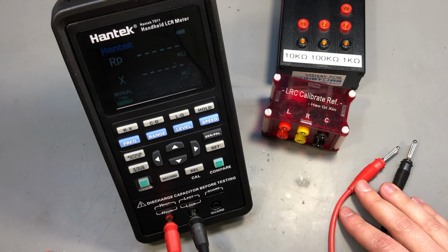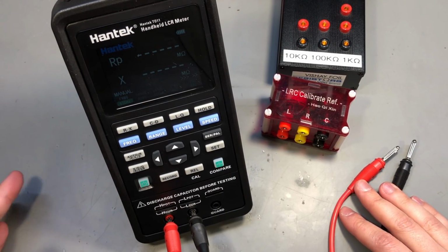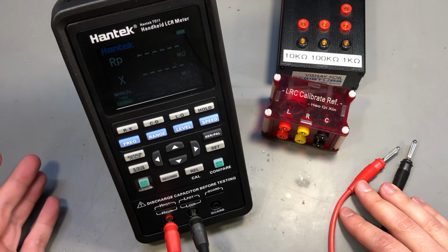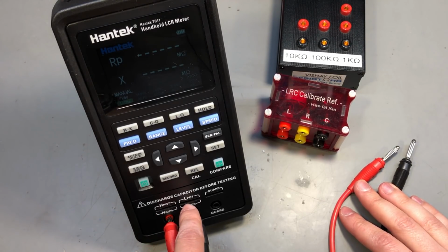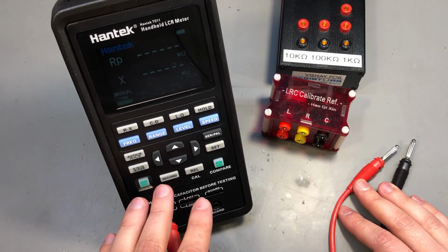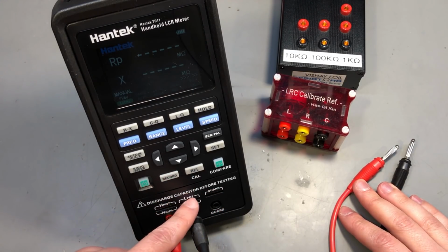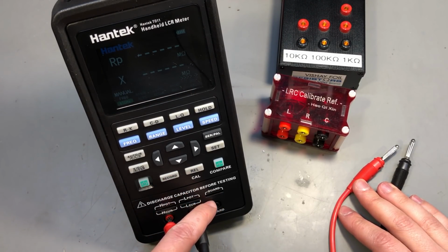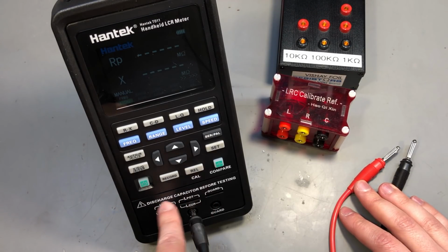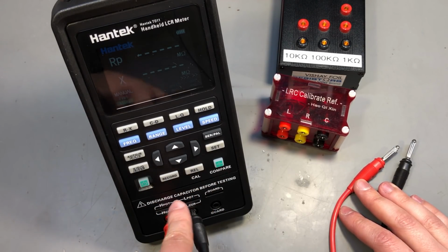Now for capacitance measurements, I would like to give a warning here. Make sure the capacitors are fully discharged by shorting them before connection to the LCR meter. A big capacitor may hold quite a lot of energy, which will be discharged into the input circuitry of the meter when inserted. As you can see, this warning is also printed right next to the input terminals.